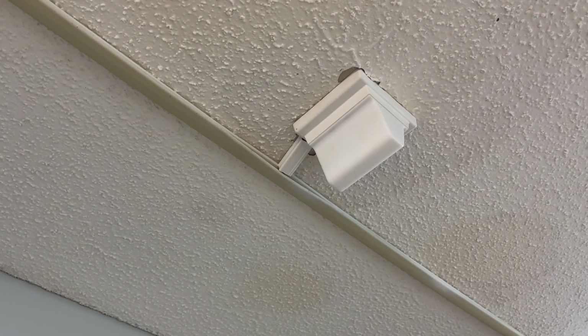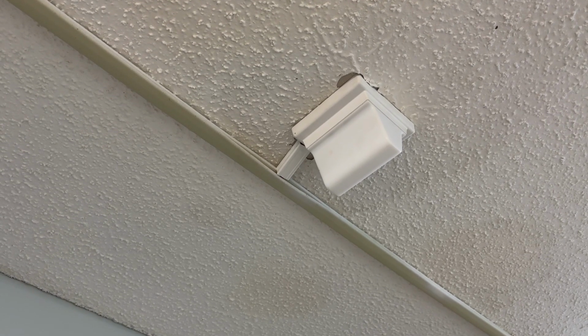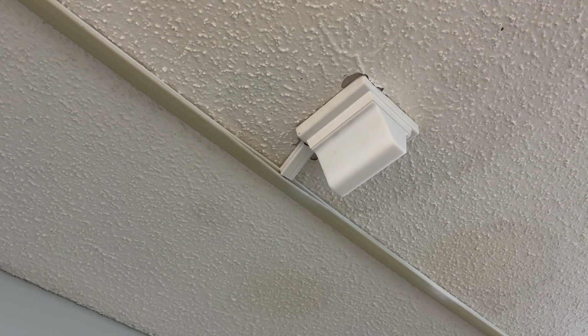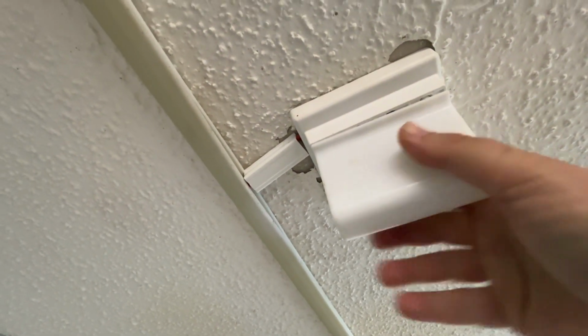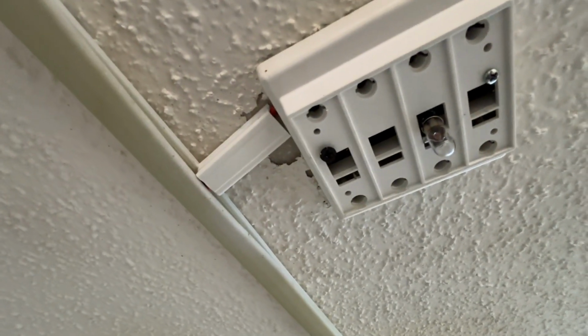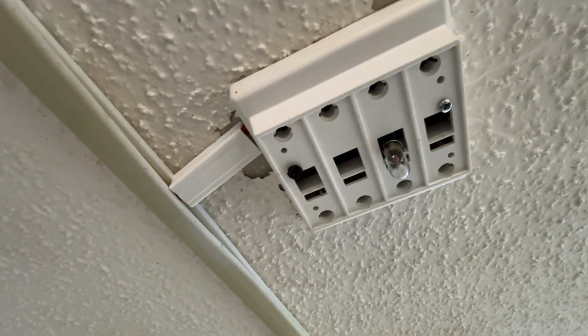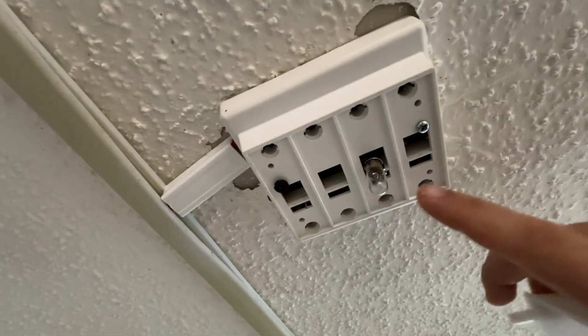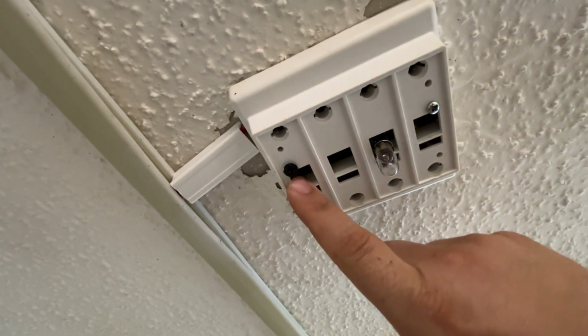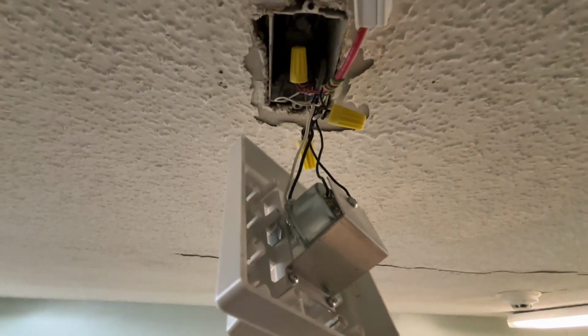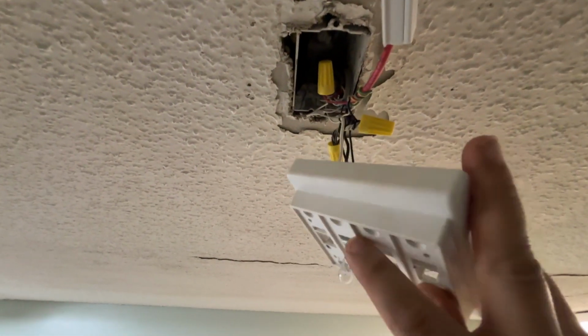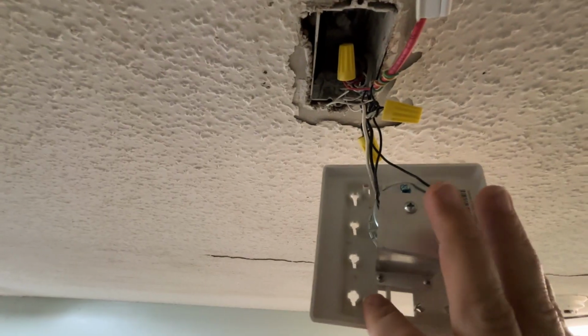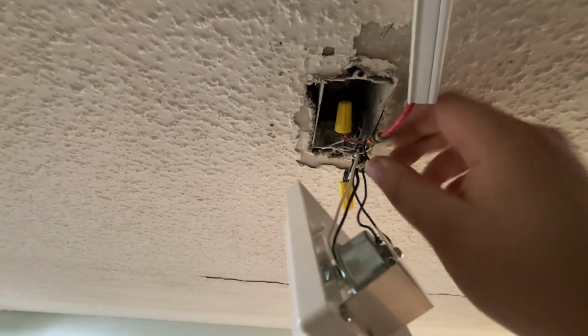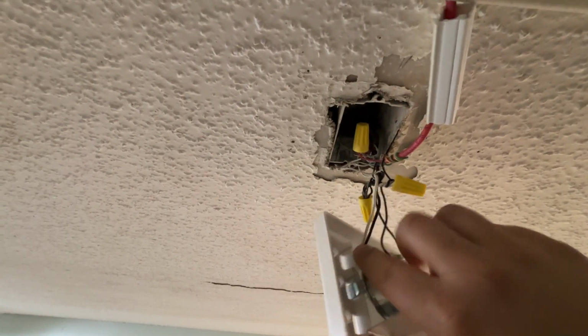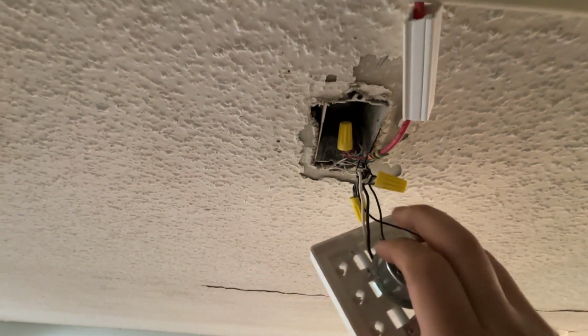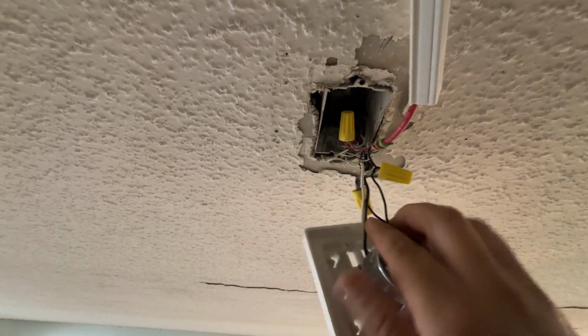On this style siren, the plastic cover simply pulls straight down, exposing two screws to remove the mount. Pulling straight down, you can see the two screws holding this to the ceiling. We remove these two screws. The wiring varies on these, but usually you will have two wires going to your light and two wires going to your siren. These can be followed up, white and black here for your light, and then you have black and black for your strobe, for your siren.